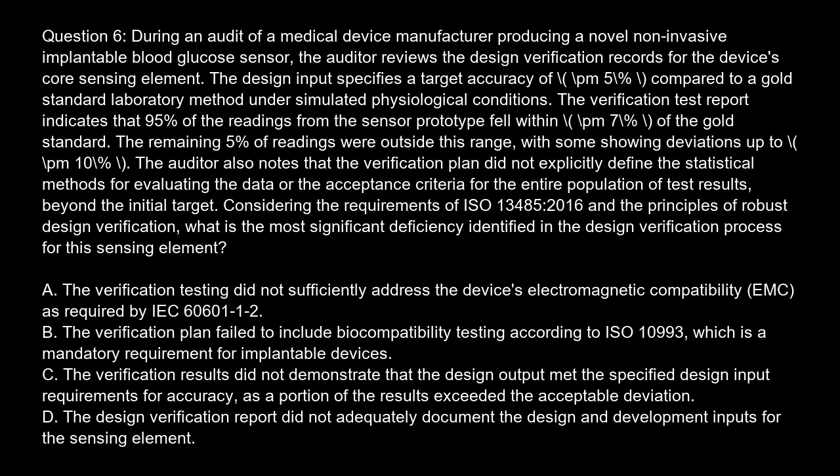Option C. The verification results did not demonstrate that the design output met the specified design input requirements for accuracy, as a portion of the results exceeded the acceptable deviation. Option D. The design verification report did not adequately document the design and development inputs for the sensing element.